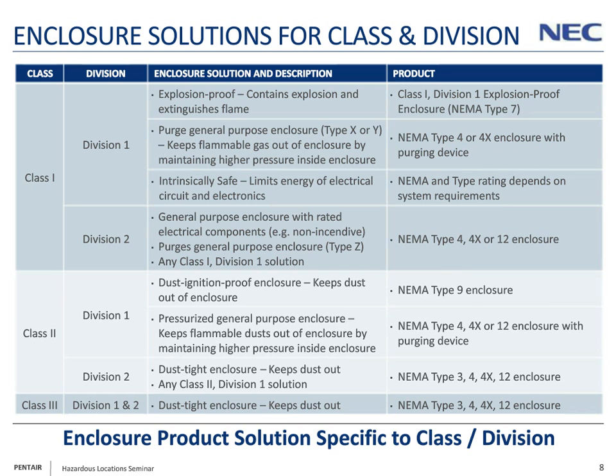In Class 2 Division 1, you can use a dust ignition-proof enclosure. It's a little heavier duty, thicker gauge enclosure called the NEMA Type 9, and the idea is they want you to be able to thread in conduit entries into the enclosure and seal it. You can also pressurize a general purpose enclosure to keep flammable dust outside of the enclosure. Class 2 Division 2 and Class 3 applications, you really just need a dust-tight enclosure, so NEMA Type 3, 4, 4X, or 12 are perfectly applicable in those environments.